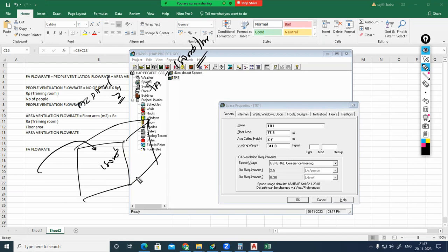Air changes per hour two means within 1 hour, two times the existing volume of air within the space will be replaced by fresh air. Then your fresh air requirement will be 2 into 190 meter cube per hour. This air changes per hour method we use a lot of times, not only for fresh air calculation but also for exhaust calculation, like residential kitchen exhaust calculation. Kitchen hood ventilation, which you will study in the upcoming classes, is different, ASHRAE 154. There we are not using this ACH value, but for residential kitchen calculation we use the ACH value. For infiltration, we calculate the ACH value. Car park exhaust calculation, lobby pressurization calculation, smoke exhaust calculation, toilet exhaust calculation, a lot of places we use this concept, ACH or ACPH, air changes per hour. Air changes per hour 7 means, in 1 hour, 7 times the existing volume of air within the space will be replaced by fresh air.